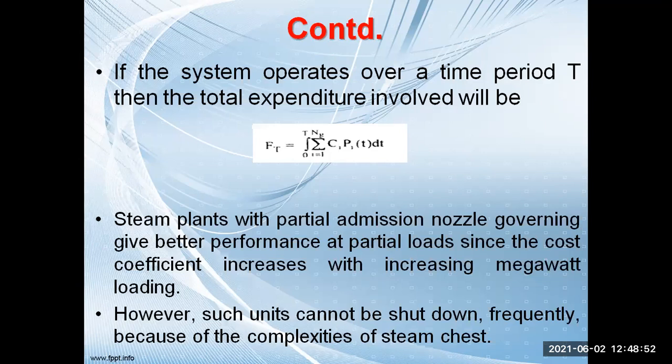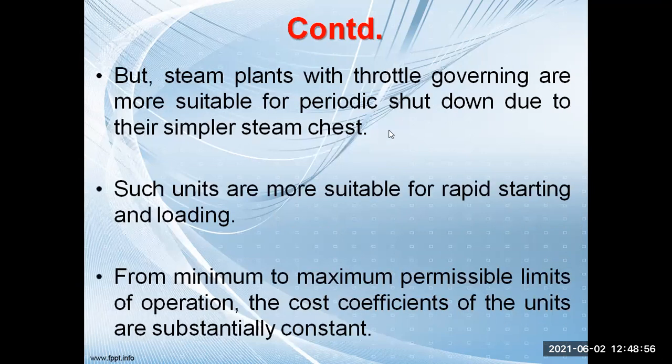However, such units cannot be shut down frequently because of the complexity of the steam chest. You have to understand one thing, that you cannot start any power plant within a second, and you cannot shut down any thermal unit within a second. It requires some time. Any thermal power plant, if it has to be started, requires some startup time, and if it has to be shut down, it also requires some time. So there is some startup time and some shutdown time. Those time periods have to be considered if you are operating any power system.